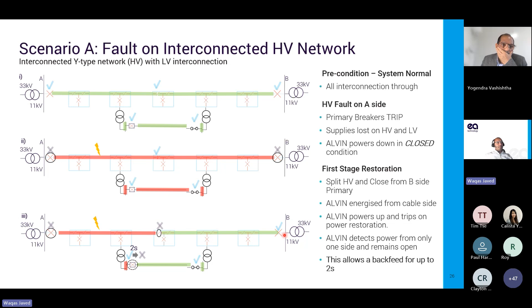So here, if you see the first figure, the system is operating normally with supply from both sides. Then in figure 2, we simulated an HV fault on one side and the upstream breaker trips, cutting supply. The LV link is still holding, but the risk here is uncontrolled backfeed or burnout of LV connectors. So what it does is the first stage restoration from the other side. The recloser device powers up from the cable side and recognizes it's only energized from one direction, so it trips open within 2 seconds to safely isolate the section.